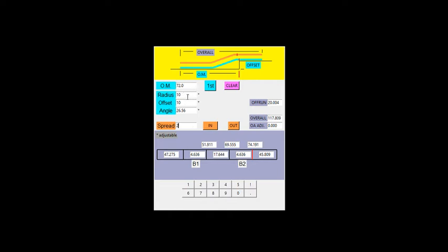Okay, so what I did though was I put more flexibility in this program, that you could come here and change these parameters here, and all this is in reference to your first conduit. So let's go ahead. If I wanted to increase the radius, okay, more radius, more gain. Okay, so this increased by 0.17 and it added to your overall here. That's the only time you're going to get a difference in the overall, is if you change something else in your original layout. Okay, and let's go ahead and reverse it back out and take it out. Now back to where I started.